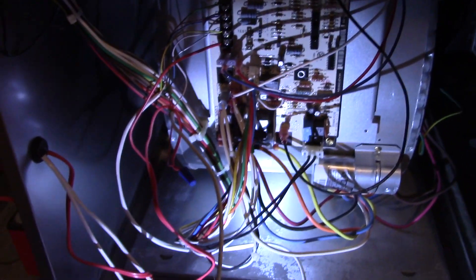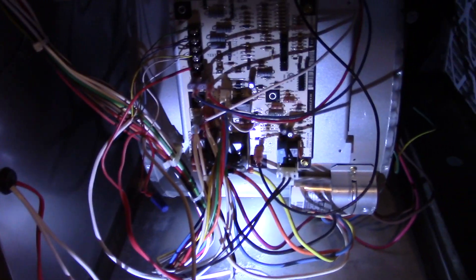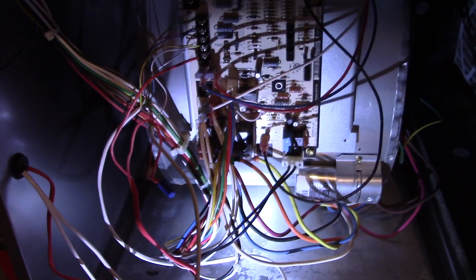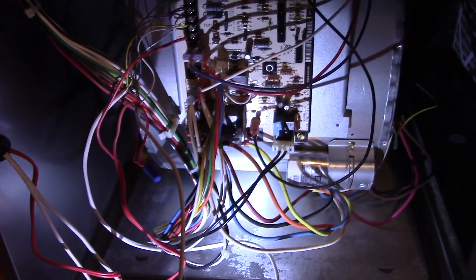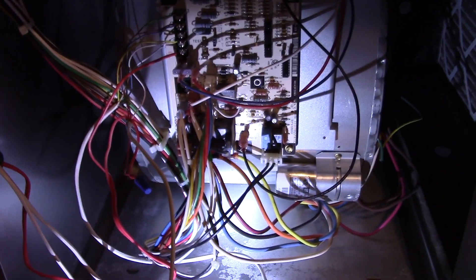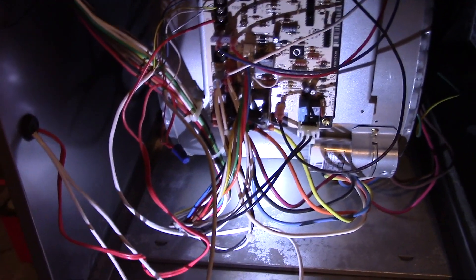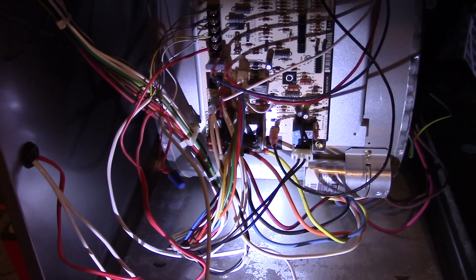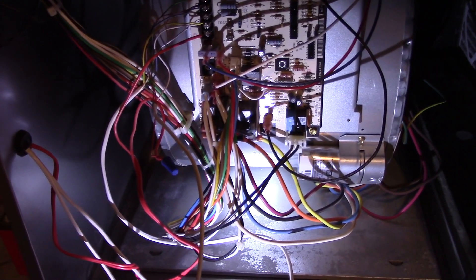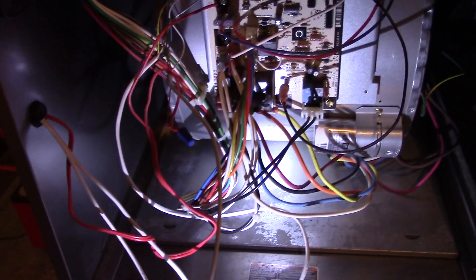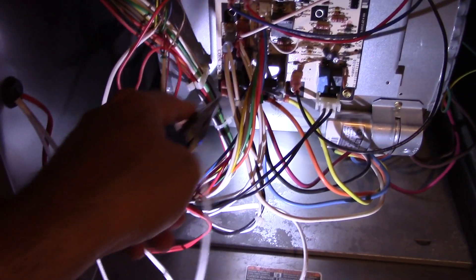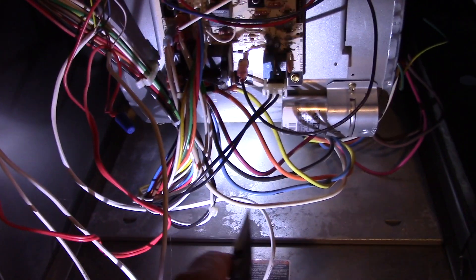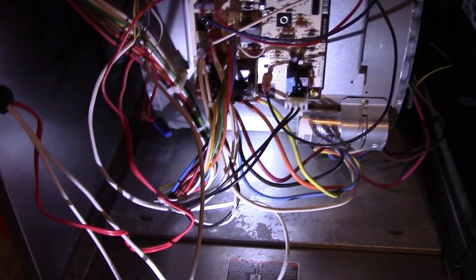Now, on the other hand, if you want to change your heating speed, generally it's okay to bring it up, more airflow through the heat exchanger, and it shouldn't cause too much heat loss because those heat exchangers are pretty powerful. If you want to change the heating speed, and let's say for example, you're not sure what color is actually going to be what speed because the wiring diagram is no help, I can show you how to basically change the speed and show you how to do a test afterwards. If you know for sure what speed you want to put on it, let's say you want to bring it from medium-low, which is the blue wire, to medium-high, which is the yellow wire.